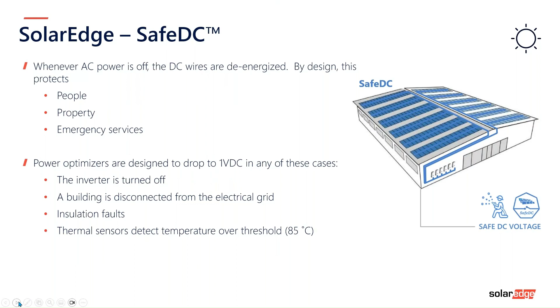And this is what it looks like in graphic form. So here you have a system, the inverter's turned off, the panels are grayed out because they're not producing, and both my speedos here, one for sunshine, which is irradiance, and the other one is for voltage. So you'll see when I press the button, we turn the inverter on, the keep alive signal is activated, and that's every, I think it's 30 or 40 milliseconds. It's basically a heartbeat, says stay on, stay on, stay on. And then once the signals get sent to the optimizers, they switch from their default value, which is SafeDC, and go into production. You can see how they are now changing color to dark, how the irradiance is shining, and you've got the power and the voltage there as well. So all good.